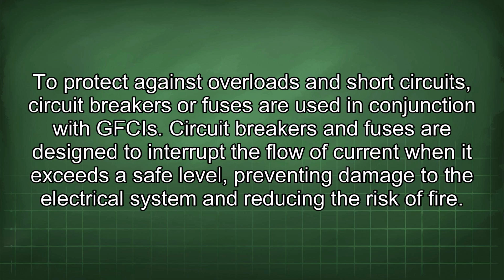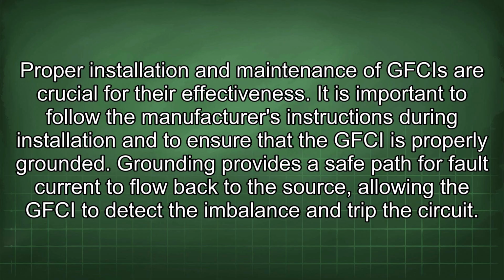To protect against overloads and short circuits, circuit breakers or fuses are used in conjunction with GFCIs. Circuit breakers and fuses are designed to interrupt the flow of current when it exceeds a safe level, preventing damage to the electrical system and reducing the risk of fire. Proper installation and maintenance of GFCIs are crucial for their effectiveness. It is important to follow the manufacturer's instructions during installation and to ensure that the GFCI is properly grounded.